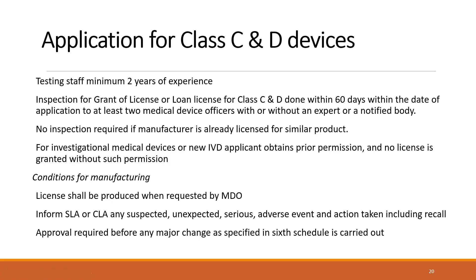Each batch of the product shall be tested prior to release. An audit or inspection book is to be maintained to enable the notified body or medical device officer to record observations and non-conformity. It is not that once it is observed, that is the end; it has to be properly documented as well. One unit from each batch of invasive medical device and IVD has to be maintained for reference for a period of 180 days after expiry of the batch.